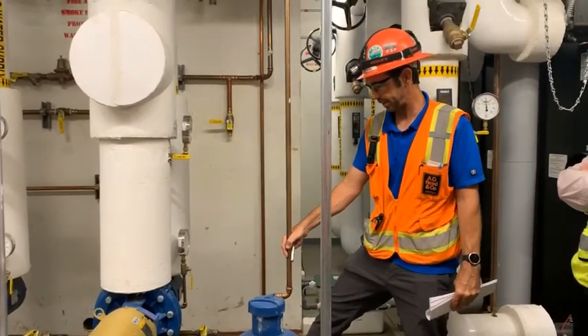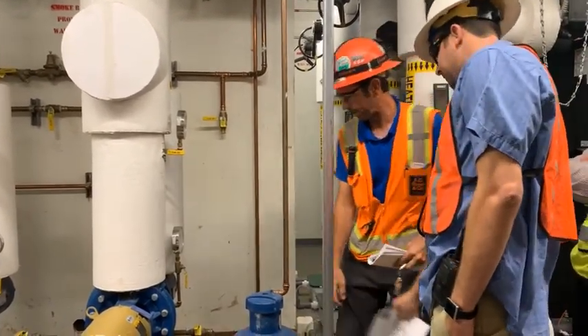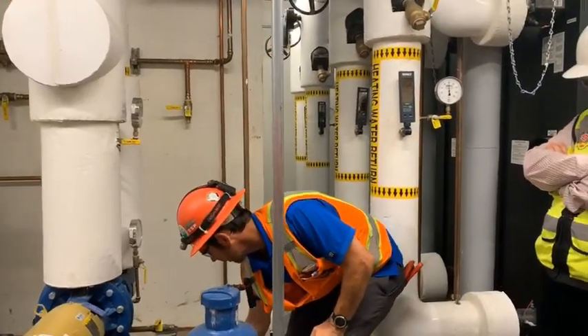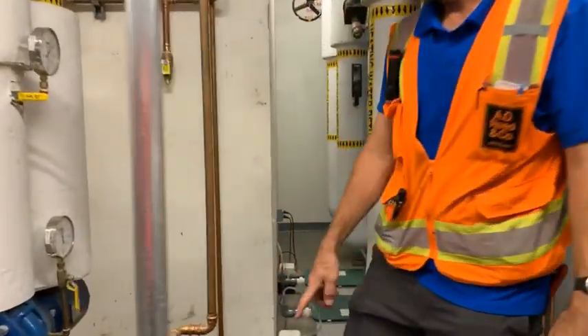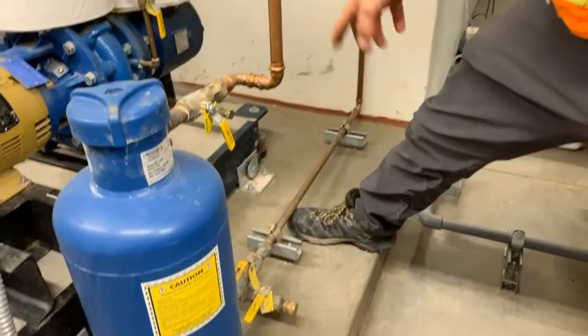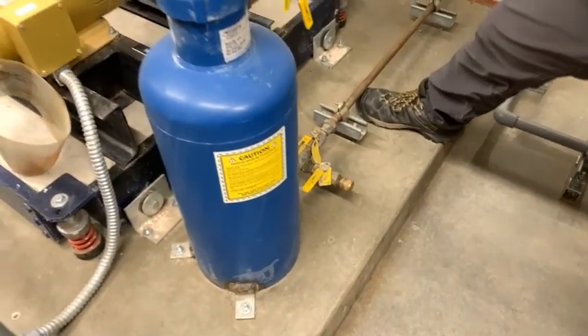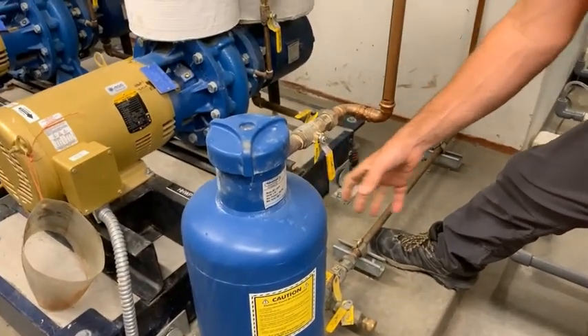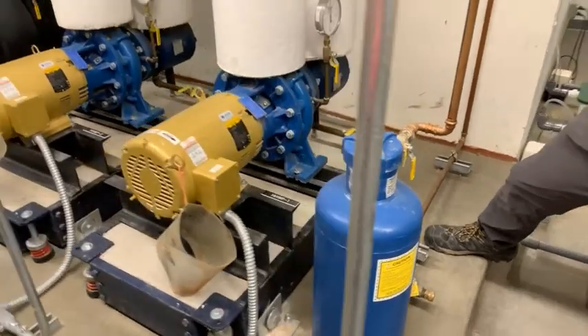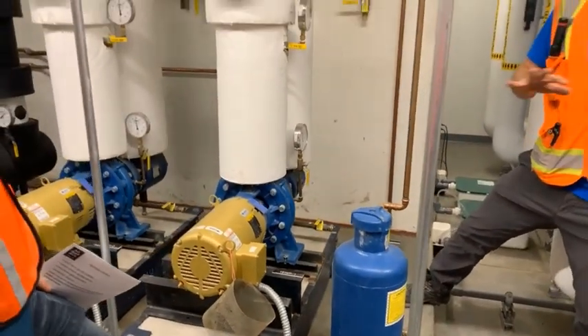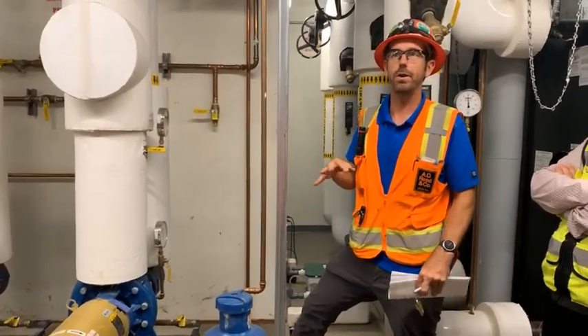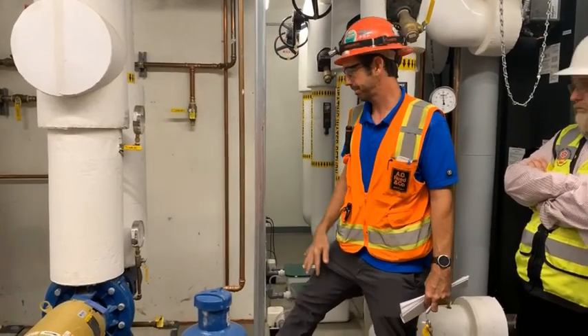And you can feel the base of the bottom one. Shut off. So somebody had shut the bottom valve for me, okay? That's why I was trying to figure out why this is cold. We just need a little bit of flow. The water treatment guys never want dead legs, okay? They never want no flow in any run of pipe.